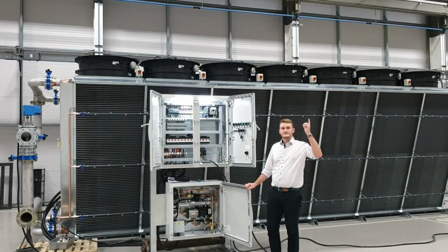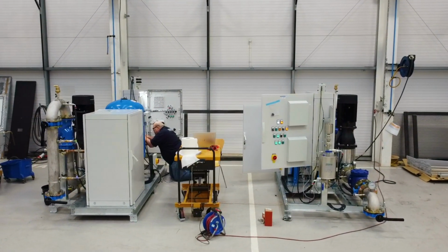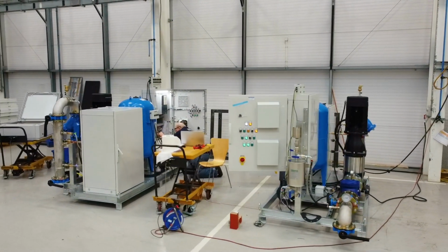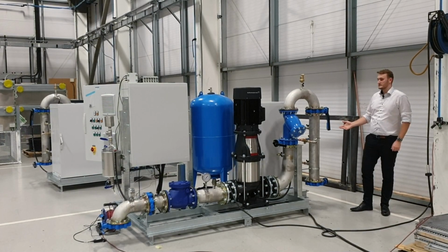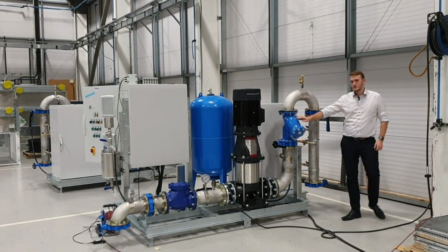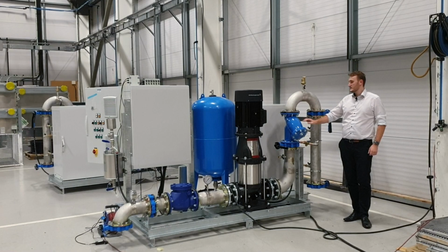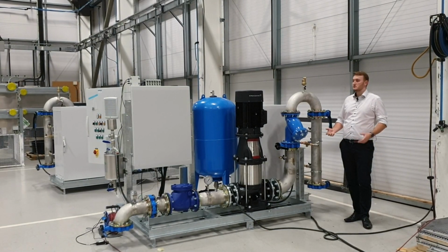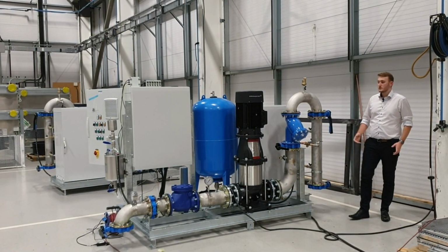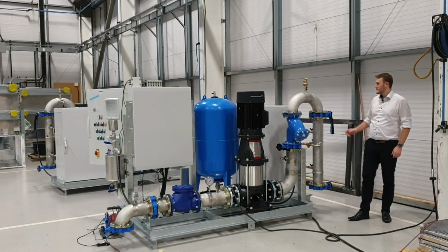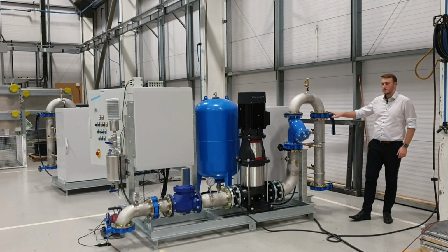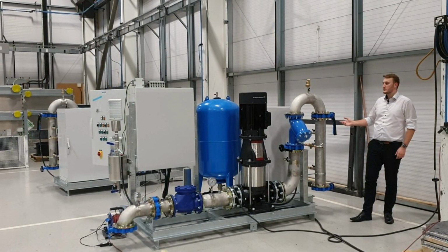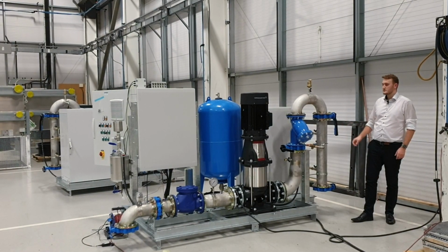This here is one of 2 identical pump sets for this system. A number of these parts are common within our range, such as the Y strainer, which we include with all of our pumps. This ensures that there isn't any sediment built up in the system. We've also added a number of extras for this, such as these isolation valves here, which can be used to isolate the flow for each component, making maintenance as easy as possible.